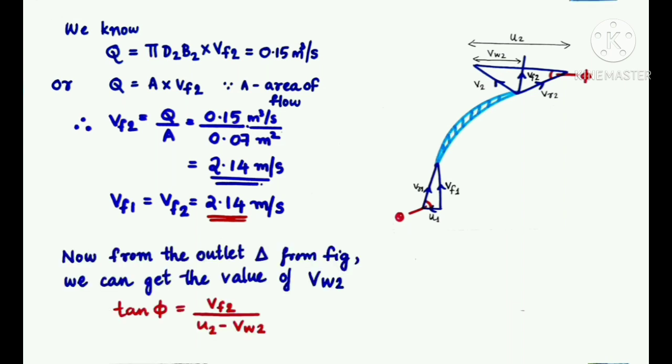Now, from the outlet triangle from figure 1, we can get the value of Vw2 which is the horizontal component of V2. From the figure, we can write tan φ = Vf2/(U2 - Vw2). We know the value of φ which is 35°, Vf2 which is 2.14 m/s, and U2 which is 15.75 m/s. Thus, rearranging, we get Vw2 as 12.65 m/s.